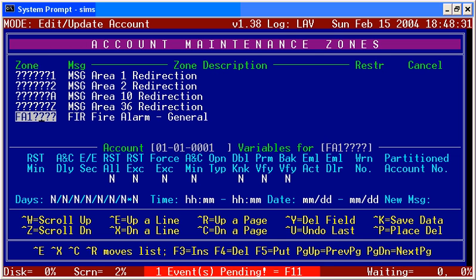And once you get familiar with it, or the panels that they're using, they'll either left justify the signals or they'll right justify the signals with preceding zeros. There's no way in the automation for us to know exactly what to do on those, because it is in fact possible to program a panel for an FA1 and an FA01. These are possibilities in panel programming for some of the manufacturers.